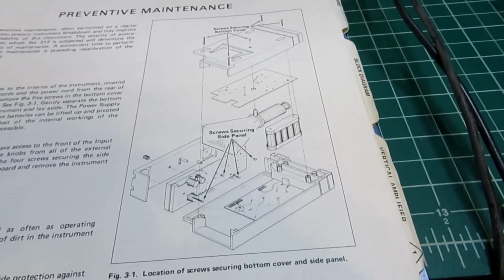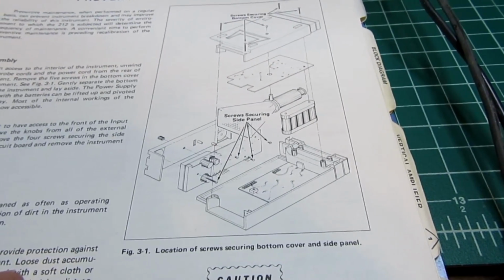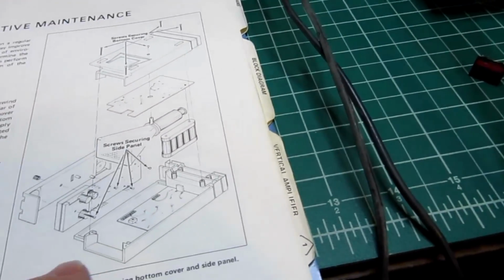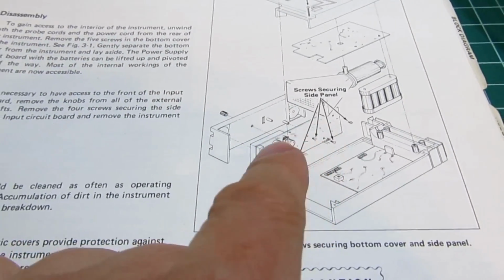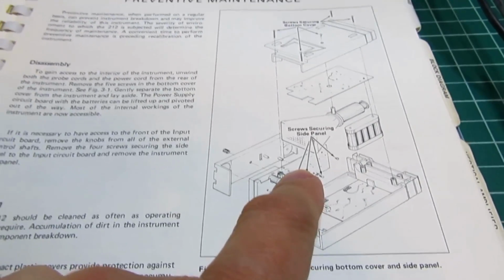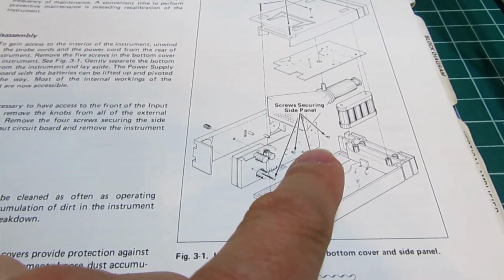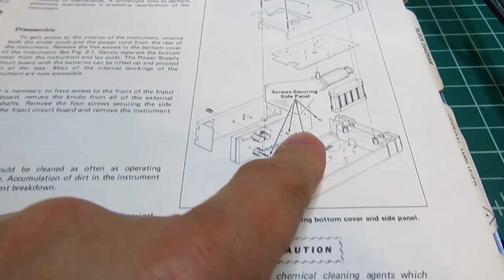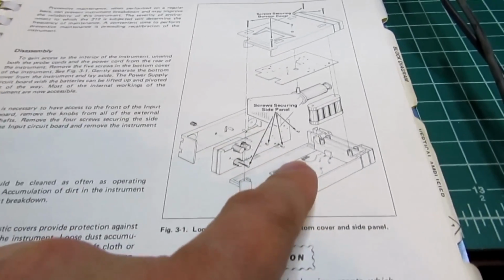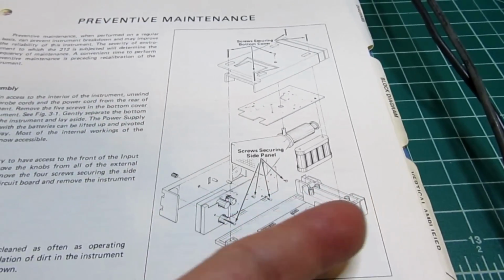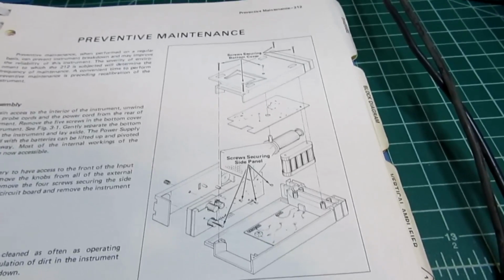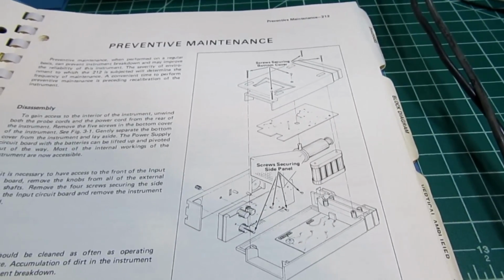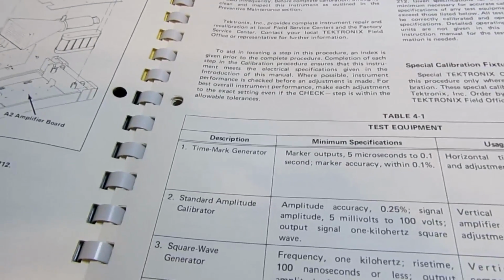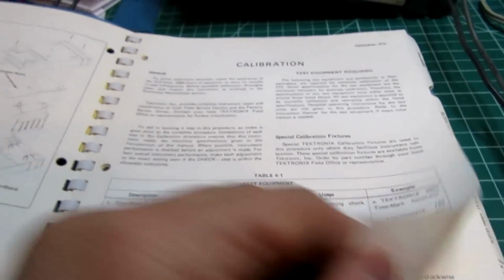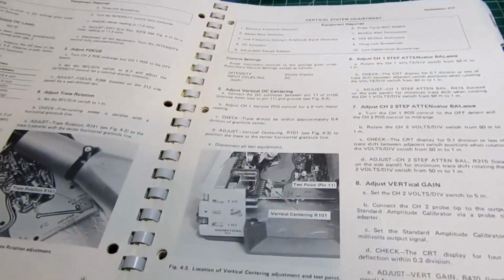On some other versions of the scope, for example the 213, which had the digital multimeter built in, there were actually 2 boards in a sandwich configuration here. One of them was very much like the single channel scope, and then the other board that was sandwiched with it had all the digital multimeter circuitry. And then they had not only a board on the top and a board on the bottom, but they had another board on this side, and that handled the high voltage, the power supply, and the digital character generation circuitry. There's calibration information here, which I won't get into.